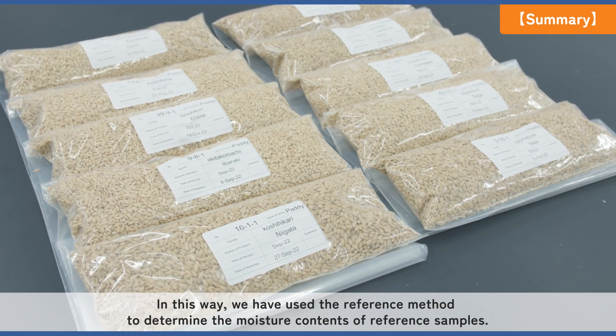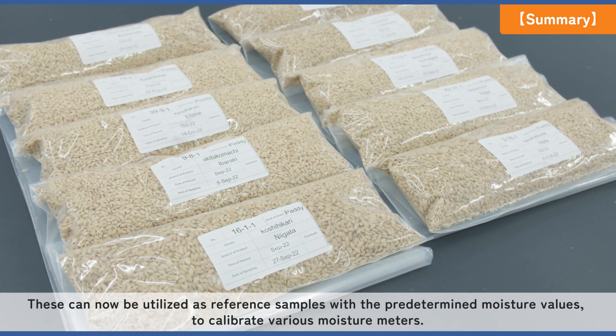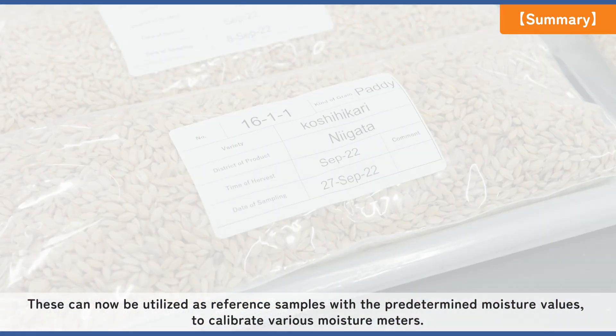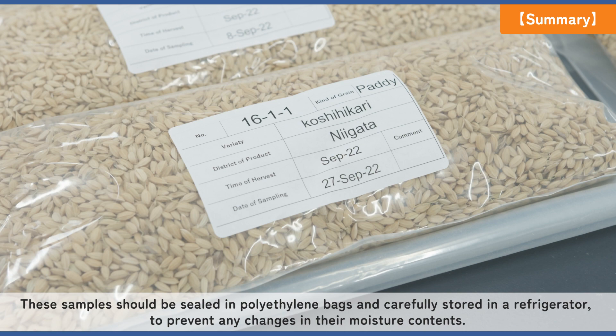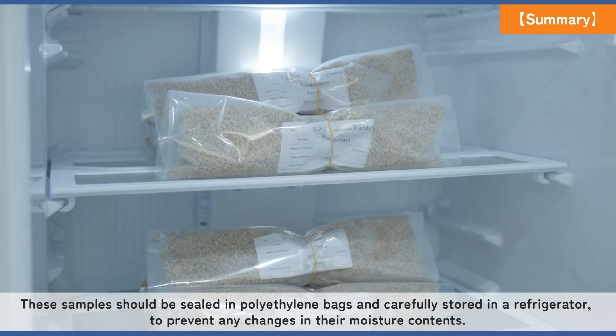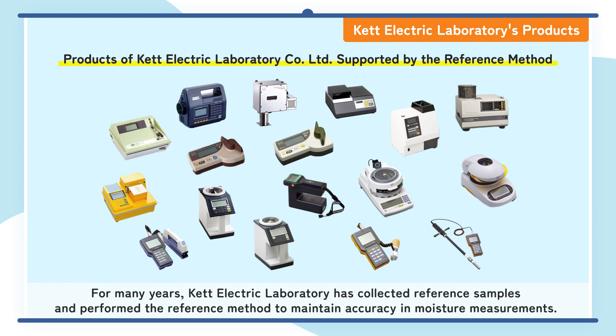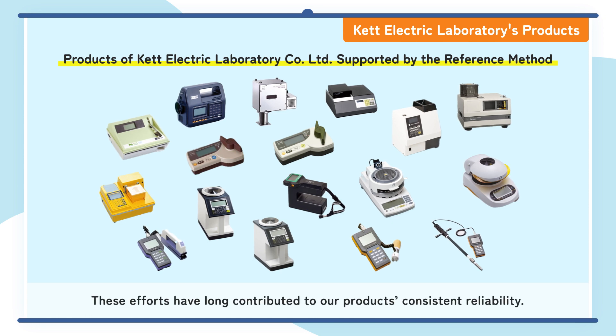In this way, we have used the reference method to determine the moisture contents of reference samples. These can now be utilized as reference samples with the predetermined moisture values to calibrate various moisture meters. These samples should be sealed in polyethylene bags and carefully stored in a refrigerator to prevent any changes in their moisture contents. The traceability system established through this reference method plays an important role in maintaining the accuracy and reliability of moisture meters. For many years, Kett Electric Laboratory has collected reference samples and performed the reference method to maintain accuracy in moisture measurements, and these efforts have long contributed to our product's consistent reliability.